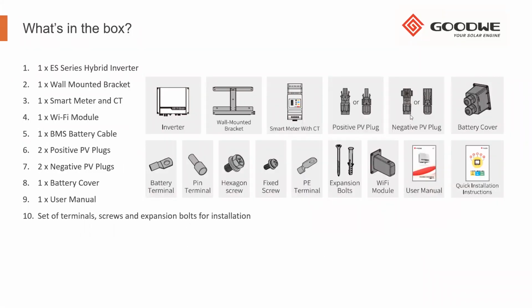So with the ES, as well as all of our other hybrid inverters, they will always come with the components that are required for the inverter to work correctly, such as the smart meter. The ES has the single-phase smart meter. The three-phase smart meter is the same profile meter, it will just come with 3 CTs. All of our CTs are 120 amp rated, so if you're using a 3-phase unit and the customer is a much larger incomer, we might have to look at using a different solution.